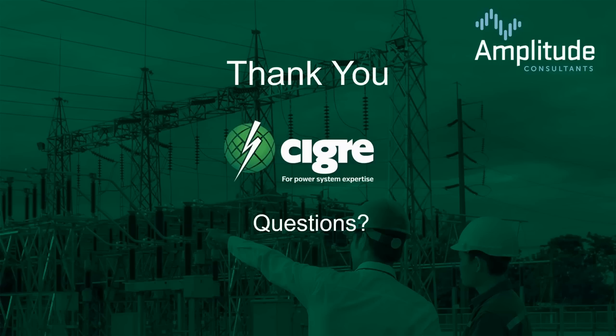The top couple that I would think of that tend to push the technology one direction or the other, one is system strength, particularly system strength at the inverter end. So if you have an interconnector and you're connecting into a weak network and you're expecting to transmit power into that weak network, you will probably avoid LCC. Nowadays, with the higher megawatt values available in VSC, you will probably go for a VSC type solution. And if you've got intermittent generation at the rectifier, you will probably go for a VSC solution. You can use LCC, but it would be a tricky thing to do.